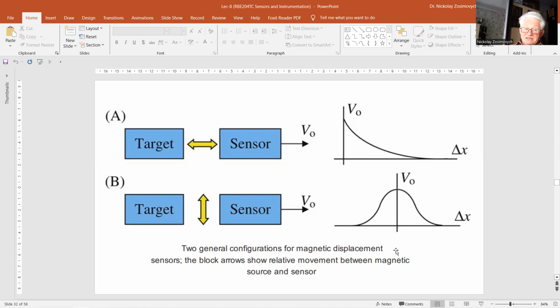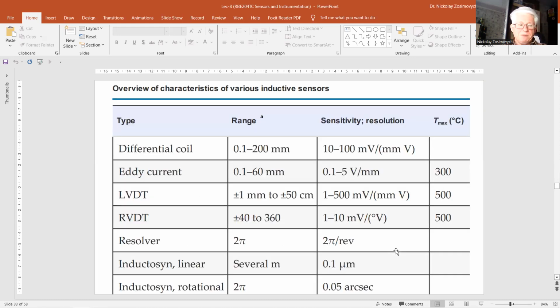The major application, therefore, is as a proximity sensor or a switch. An important parameter is the switching distance, which depends on the mechanical layout of the sensor, but also on the dimensions and material of the moving part. In commercial systems, the switching point can be adjusted over a limited range by varying the sensitivity of the electronic interface, as you can see in this table.